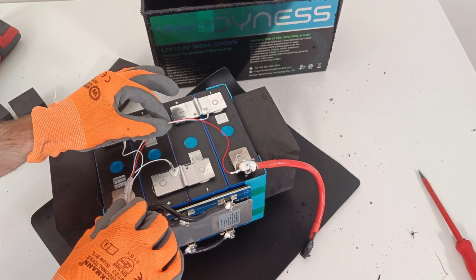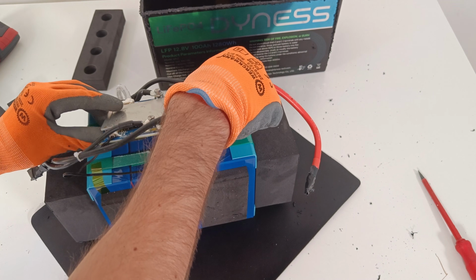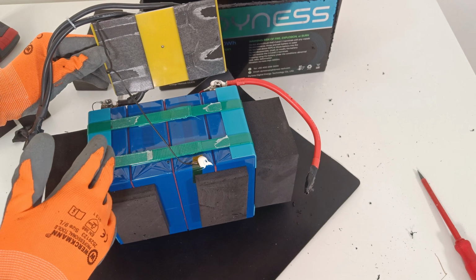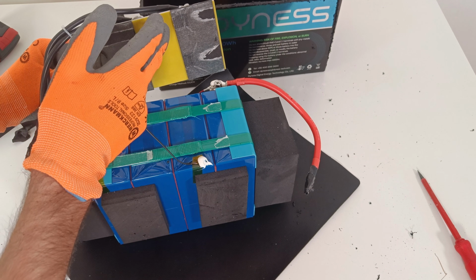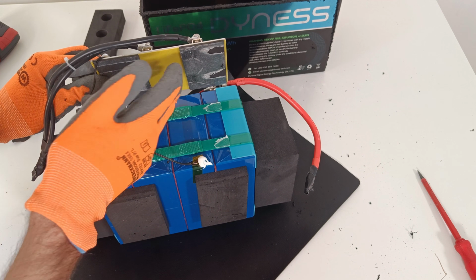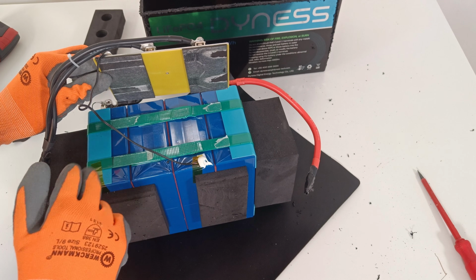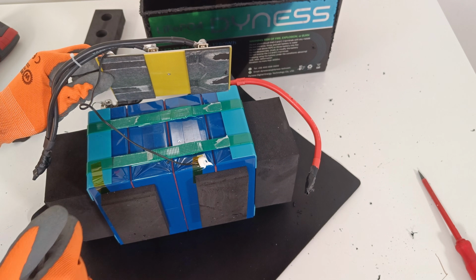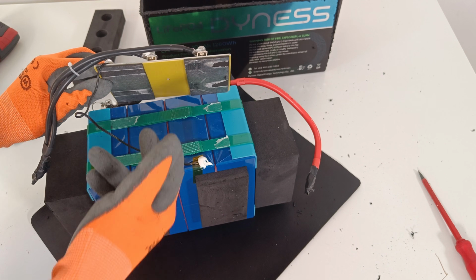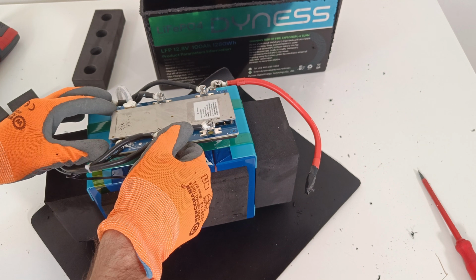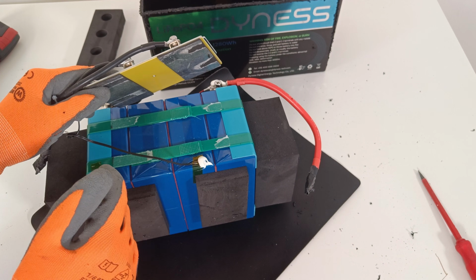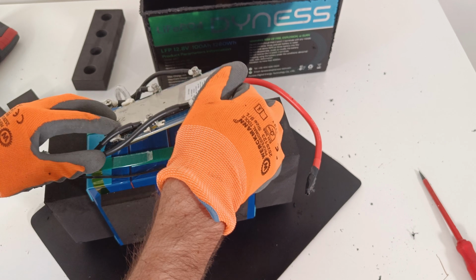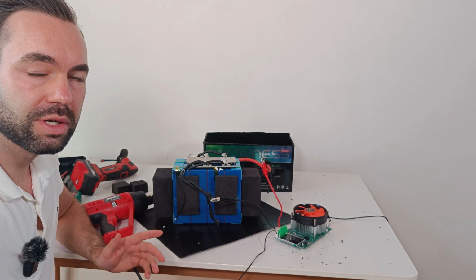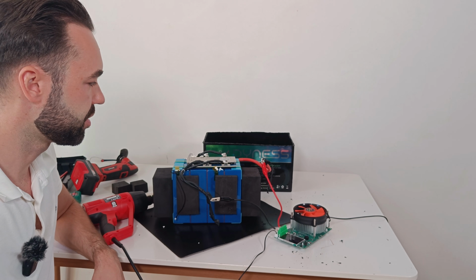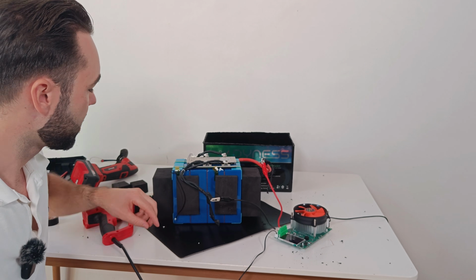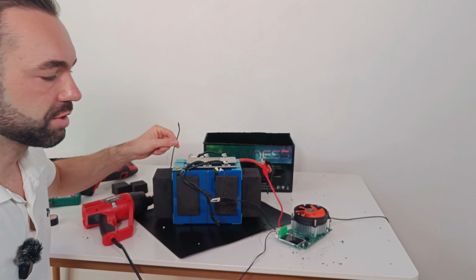And then we can see the balancing cables. So the BMS has a fiberboard underneath with some insulation pads as well. And they were on these straps. So I think that's sufficient. Let's now do the temperature tests of the BMS. Let's do the high temperature protection test first. I will add a 10 amp load and I will use a heat gun to heat up the temperature sensor.